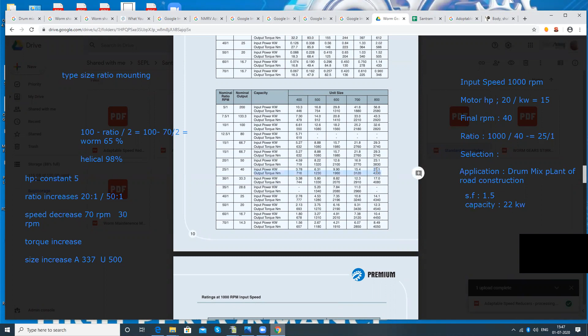Let's go back to the catalog. So it is 15 kilowatt into 1.5. 15 into 1.5 will give you 22. So the safety factor SF will be 1.5 and the required kilowatt capacity should be around 22 kilowatt. Then you can see 22 kilowatt in 25 to 1. Yeah, this is 21.1. That is nearest. So what will be the resultant output?